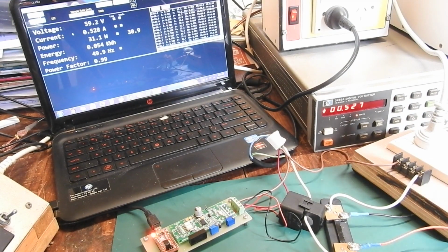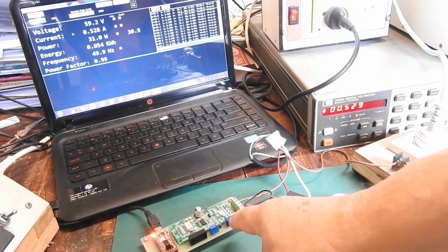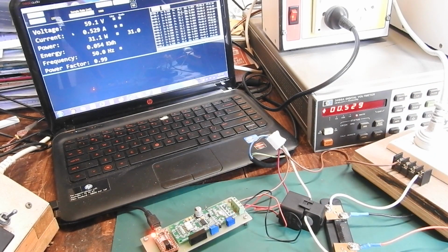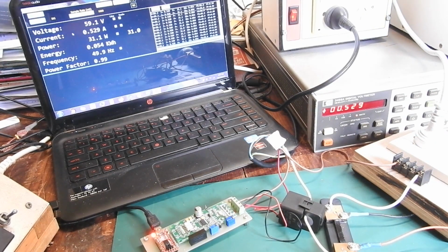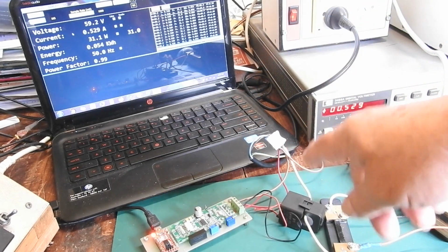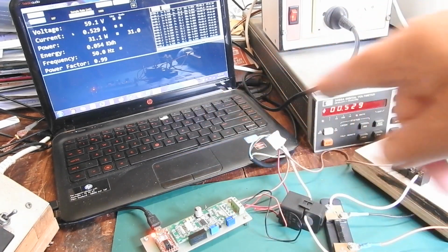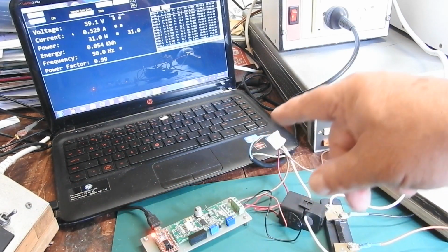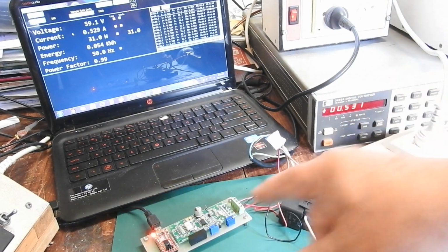So yeah, this current transformer burden resistor thing has got whiskers on it, and in the back of my head I knew there was more to it than just adjusting the value of the burden resistor. A bit more nuance than that. Also, current transformers have a linear response until you saturate the core magnetically, and then it flattens out. At the low end, they also have a curve before they hit the linear part.